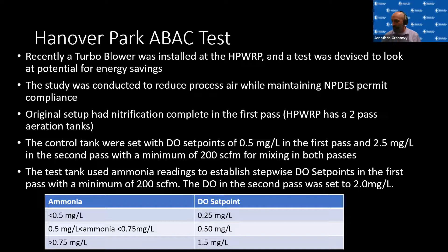You can see on the chart below where we had our set points and how we were going about it. One thing is the mixing - we don't have mixers in our tanks. We have to keep our solids in suspension, and we have a ceramic plate spiral roll configuration at that plant. So it's important not to let the solids settle on the plates, or else it will lead to a lot more problems.